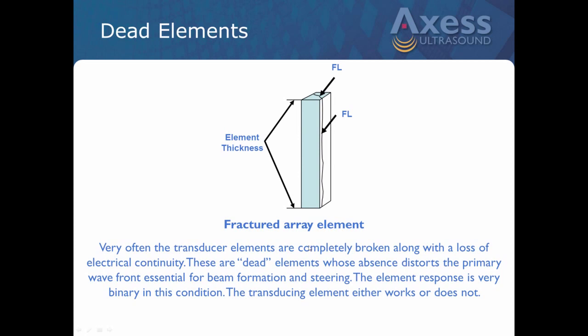I'm going to speak specifically about PZT arrays with individual elements. A true dead element is one that is completely broken or cracked. This is a representation of an individual element, and you can see it has a crack through it. Keep in mind there's a wire connected here, hypothetically all the way through the system, to fire and receive signals from this element.